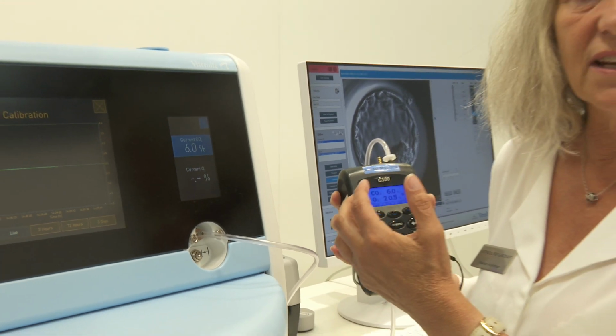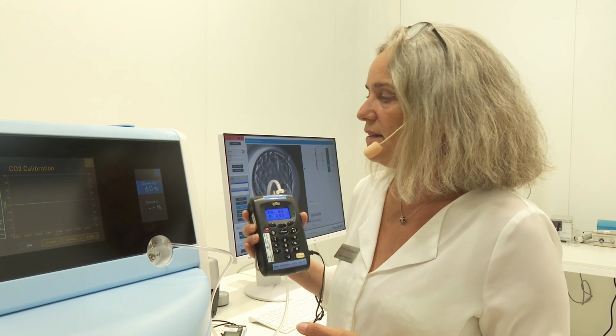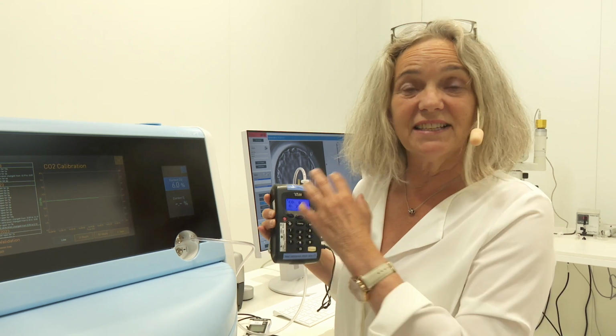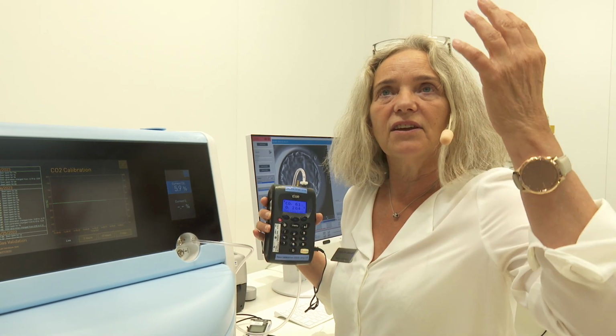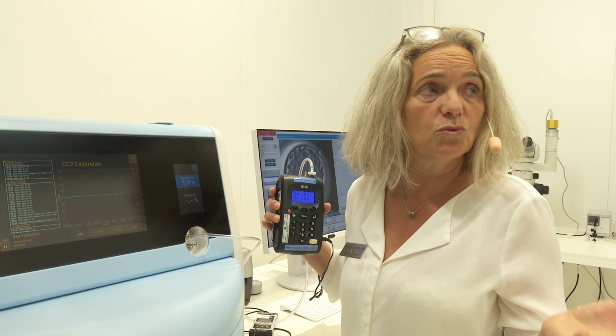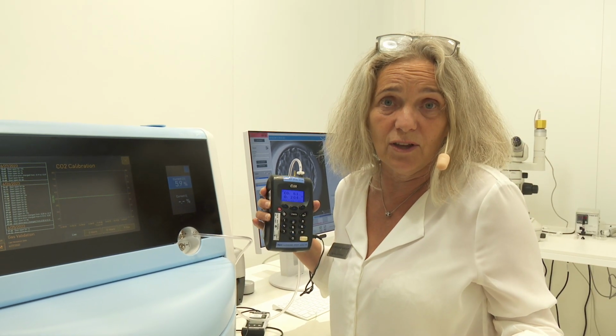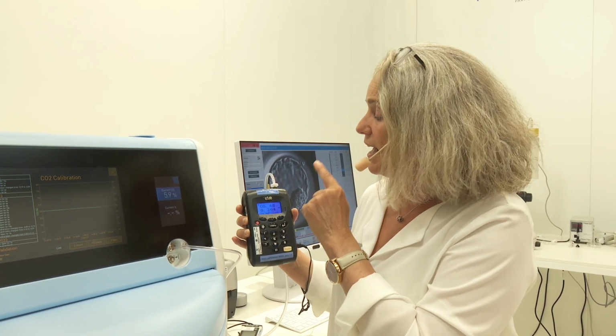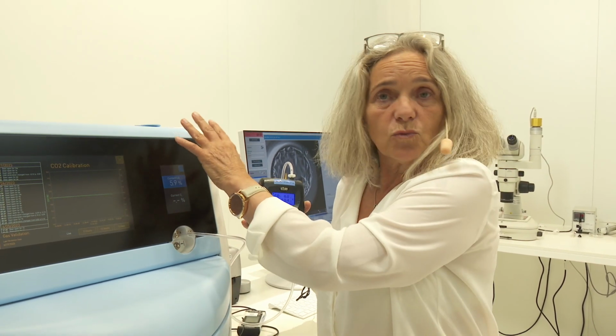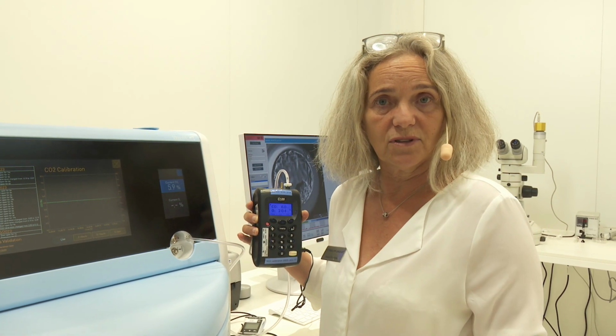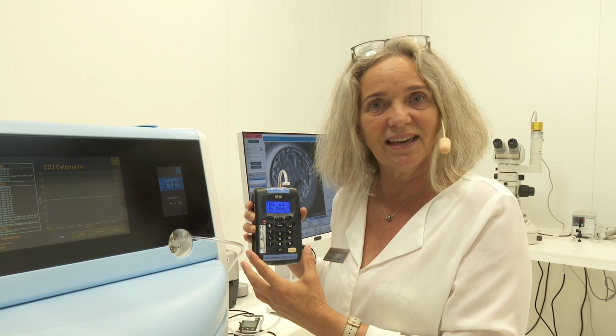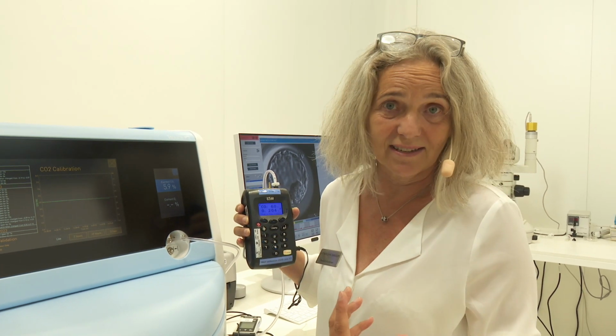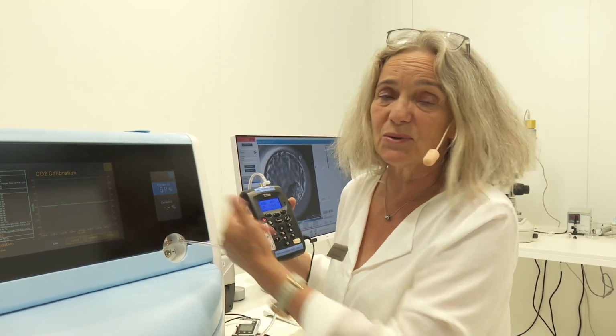But in case, let's pretend. First I would say, if it's out of range, then the first thought I would have is, is my analyzer calibrated? But it could also be that the outside partial pressure, due to weather that is very high or low pressure, will actually affect your analyzer measurement. So then I would do it the next day when it's back to normal. We should not worry about the EmbryoScope. It takes that into account. But if the analyzer is not taking this into account, you could start calibrating in the wrong direction. So don't do that.